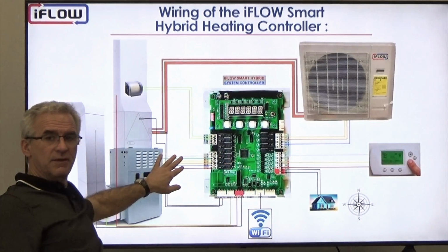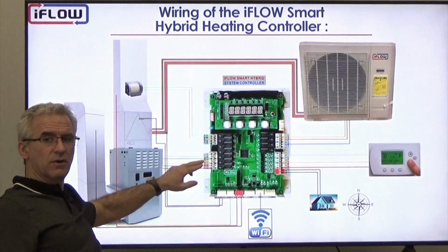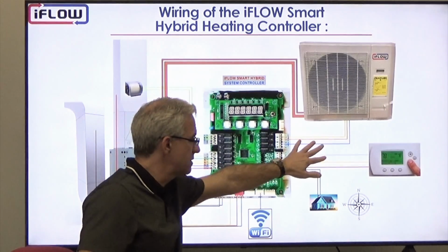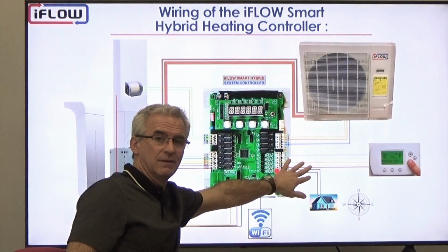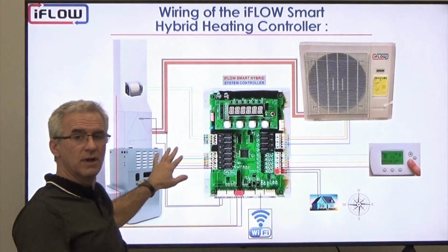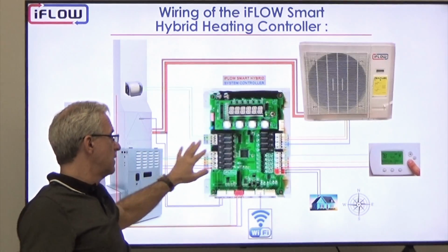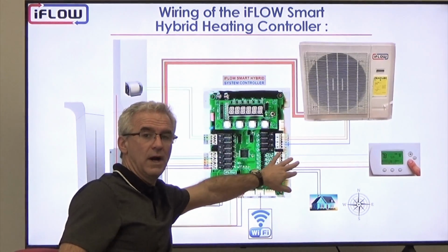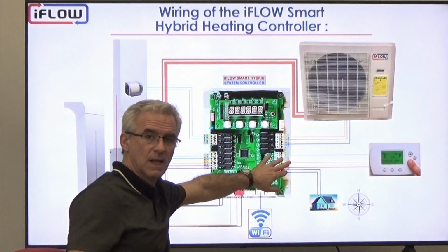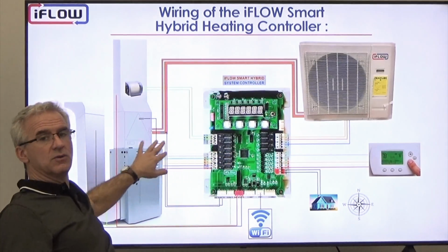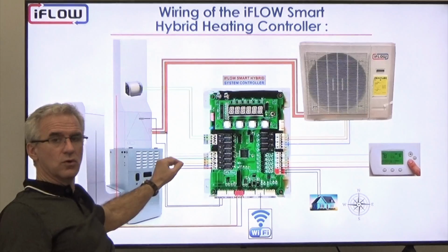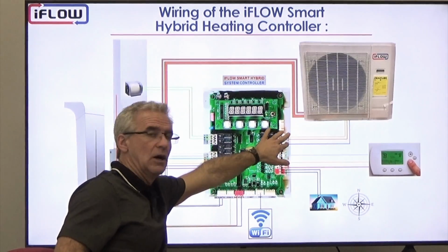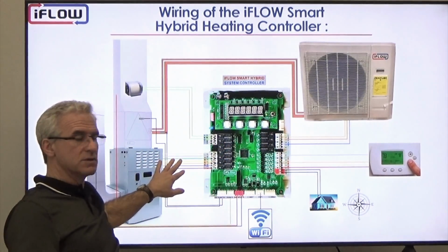On this side, on the left side, we have the connection to the furnace. So this thermostat wiring originally would have connected directly to the furnace. In this case, all we're doing is we're wiring that now to our controller, but then we're wiring out to the furnace as well from our controller. So input, then output to the heat pump, output to the furnace.